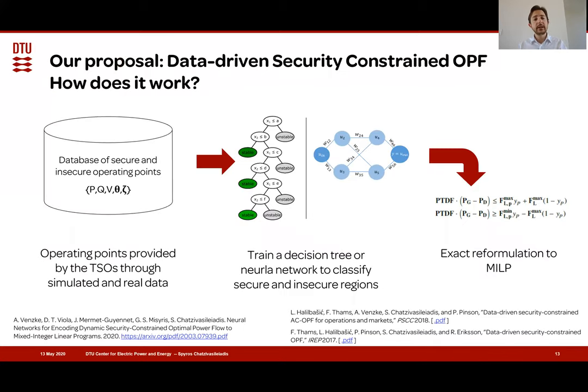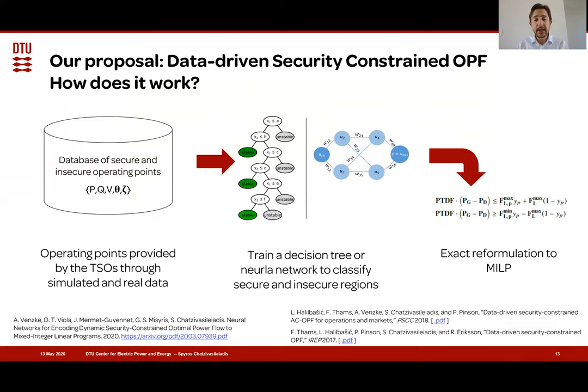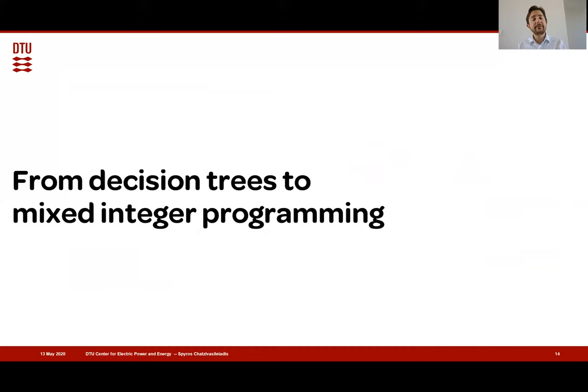What we propose instead is to create a database of secure and insecure operating points. Part of it can be based on historical data from TSOs — transmission system operators — but they can also be generated from large sets of simulation data that operators use to assess the security of possible operating points. From that, we train a decision tree or neural network that classifies these points as safe and unsafe and infers the true stable or secure region. Through an exact transformation, we convert this information into constraints that fit into a mixed integer linear program.